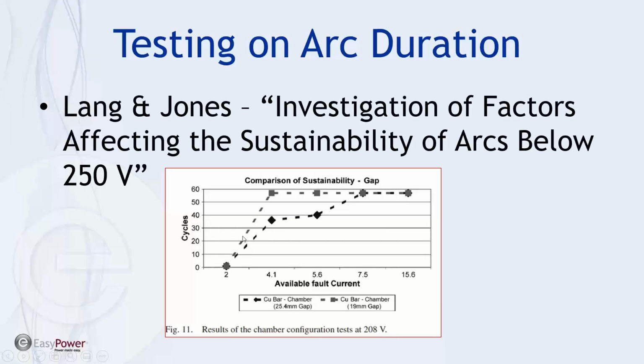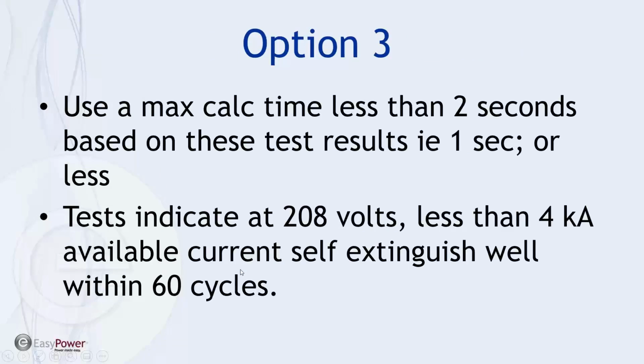And if I have any situations where I have this voltage and this current, there's a potential that my max calculation time could be set at less than 2 seconds. For instance, 1 second, and still have 100% guard band on what my incident energy is. Now, this doesn't eliminate the need to do data collection, but it could have some impact on my decisions about daily wear and hot work, and again, what my bandwidth is as far as personnel and maintenance crew.